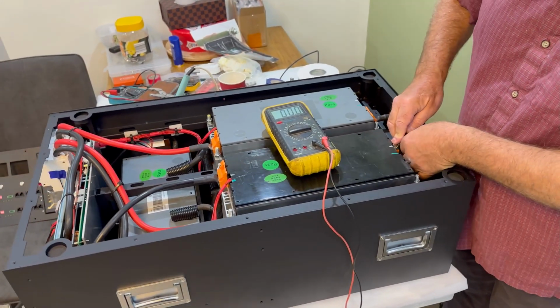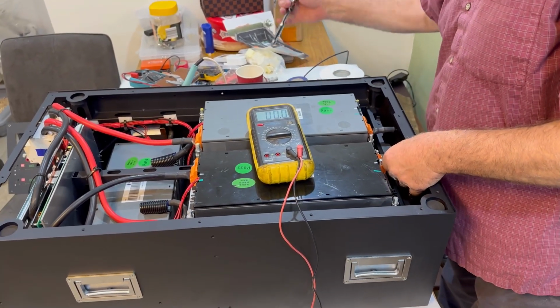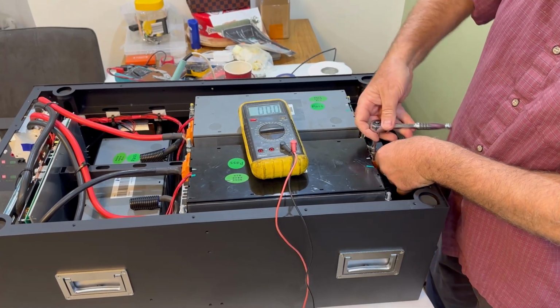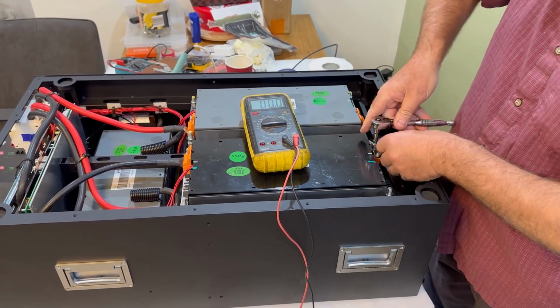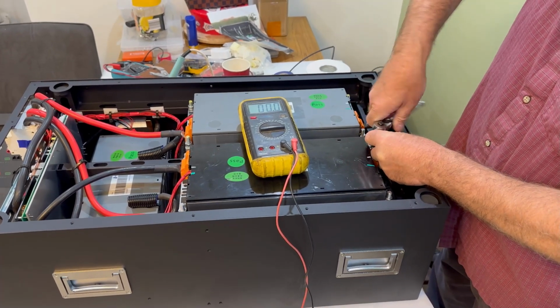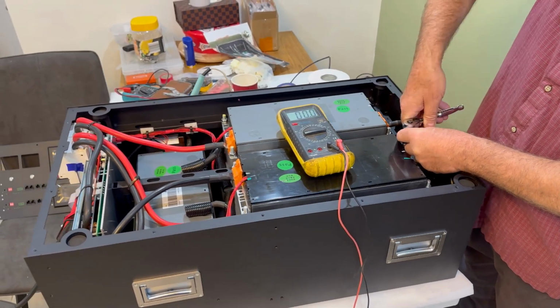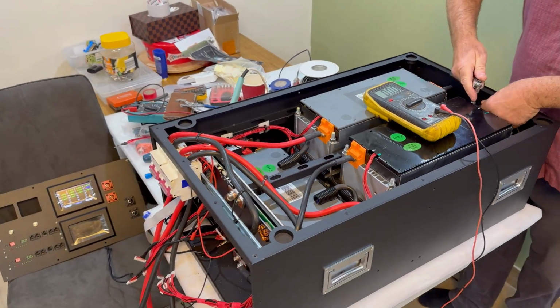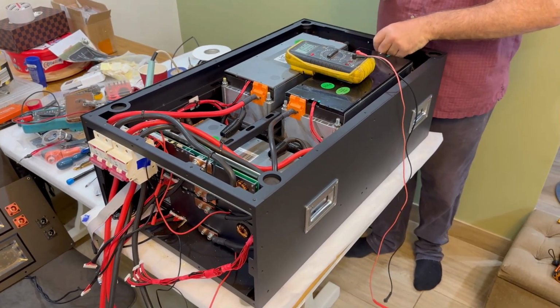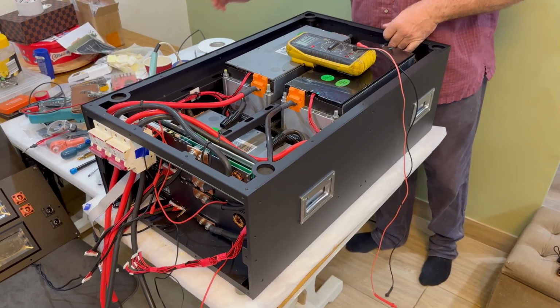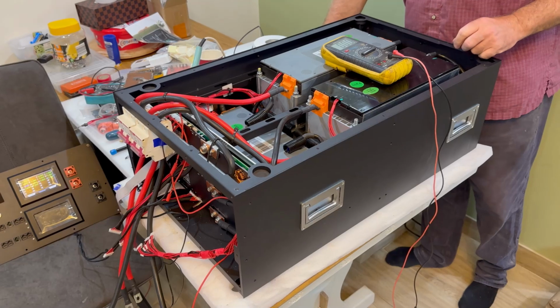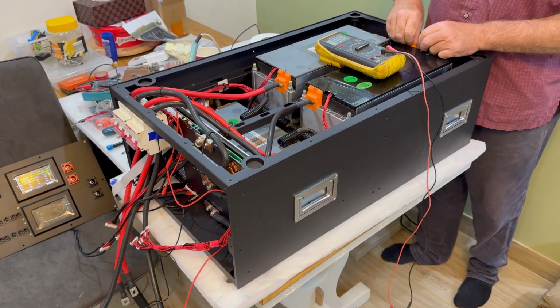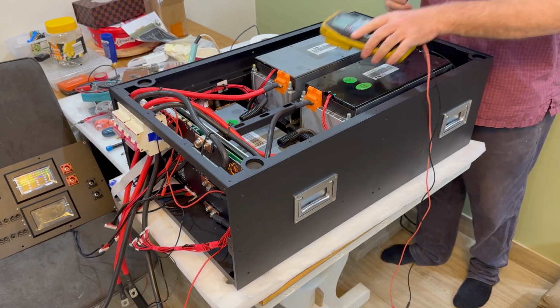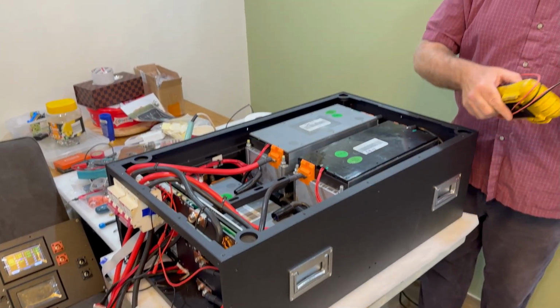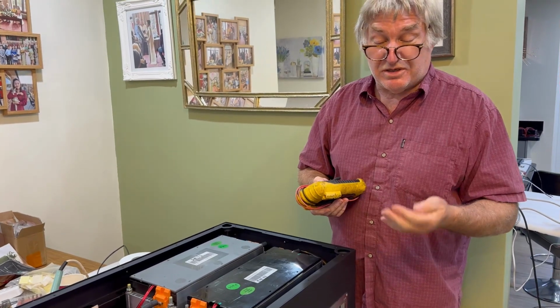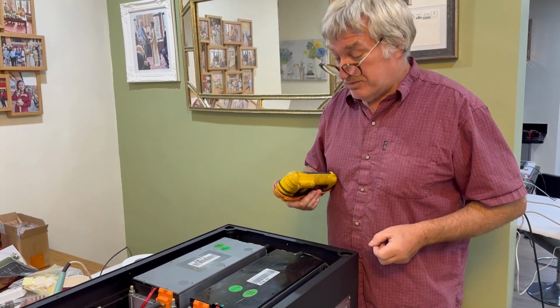When working on the system or doing any work at the front, it's always advisable to remove these link cables between the battery pack at the back, which gets rid of any power at the front while you're working on the live connections up there. There's a lot of current available in these batteries, especially with this size cable, and it will be a rather nasty arc and spark if you're lucky. It can also hurt. Even though it's low voltage at 48 volts, the arc tends to burn bits of your fingers away and things like that. So always be cautious.